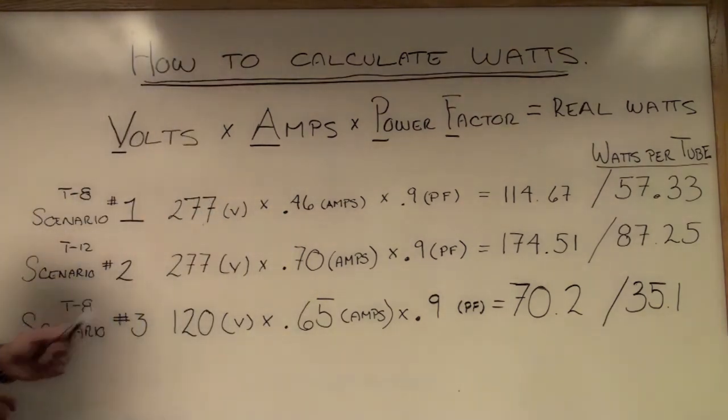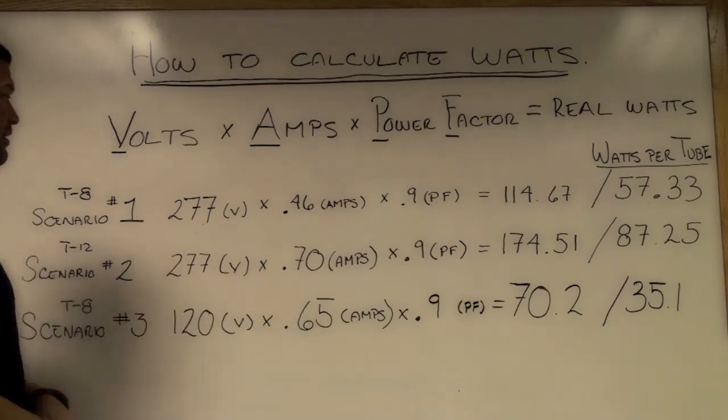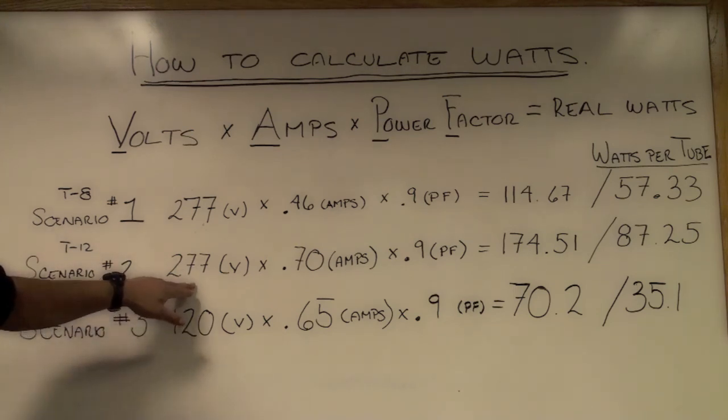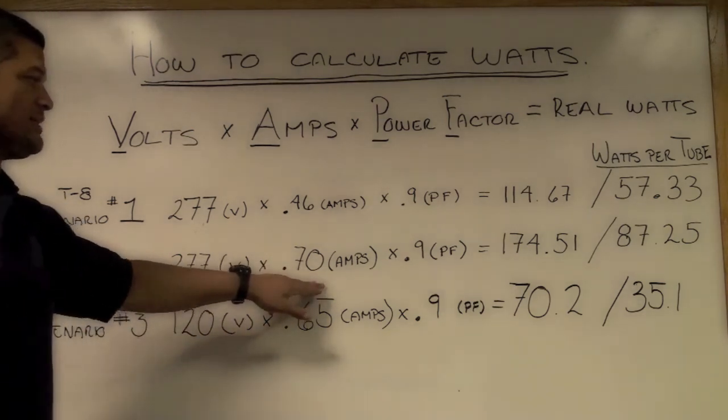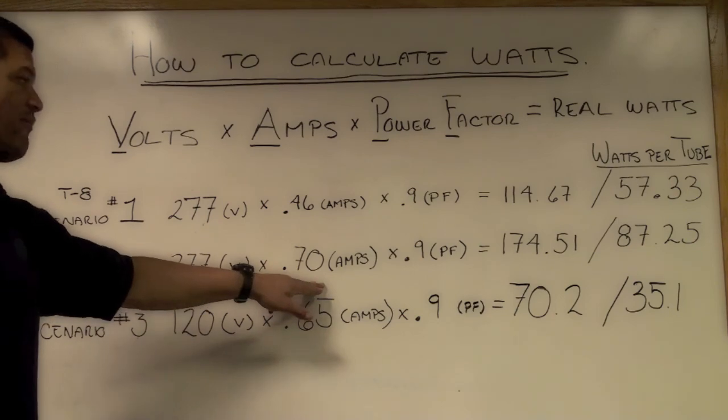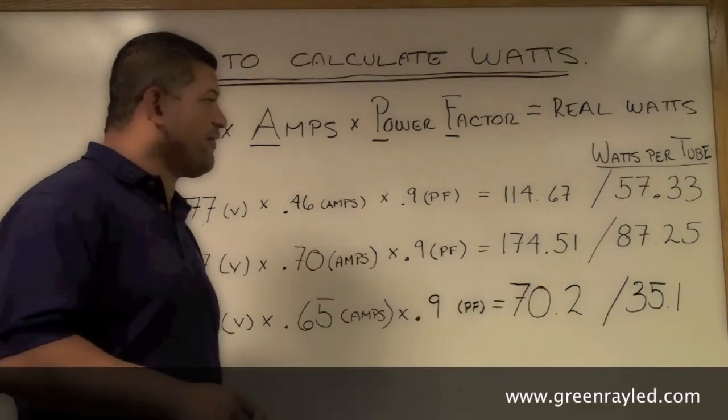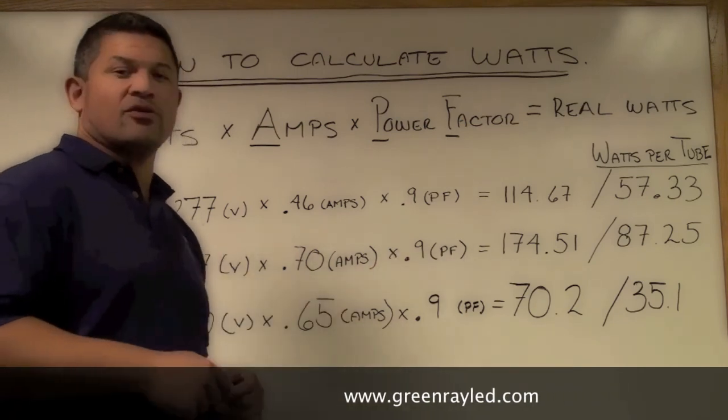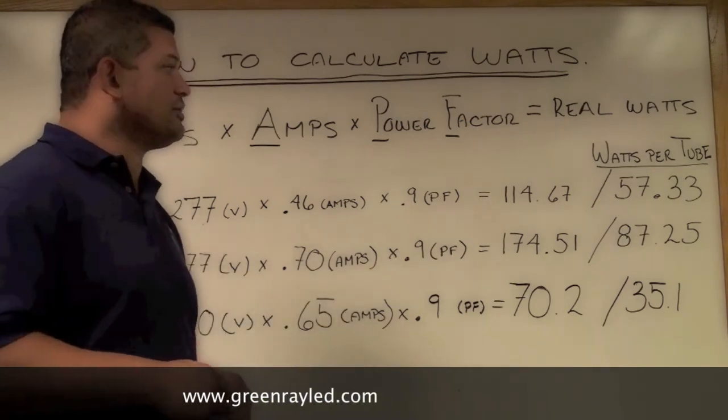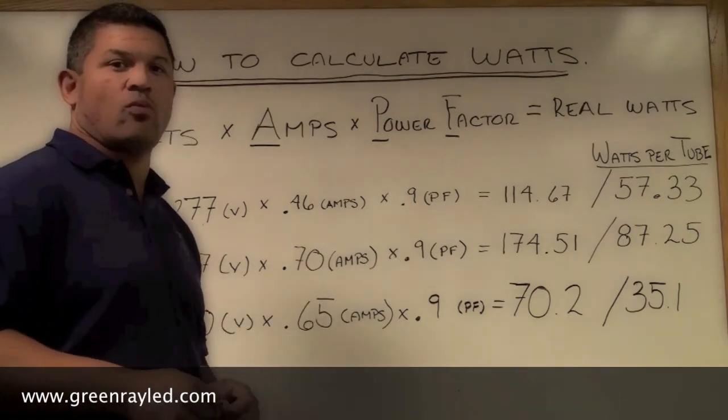The second scenario, and you'll see it on the ballast that I have, is a calculation that we're taking if the amperage went up to 0.7. 277 are the volts that we're using in our lights. 0.7 is the factor for amperage times 0.9 gives you 174.51 and that would bring your calculation per tube to 87.25 watts per tube.